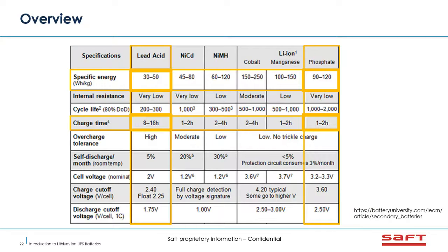And then just a quick overview, tying in some of the other technologies. Again, I'll look at a few key things. Again, just to summarize the energy density, looking at lead acid versus, let's say, a phosphate battery, you're looking at 30 to 50 watt hours per kilogram versus 90 to 120 for a phosphate lithium-ion battery. Charge time, very important for some customers to get the uptime back to the system. Typically you're at 8 to 16 hours for a lead acid battery versus a phosphate battery that's typically done in about 1 or 2 hours. So much faster recharge on these lithium-ion batteries compared to lead acid or nickel cadmium batteries as well.